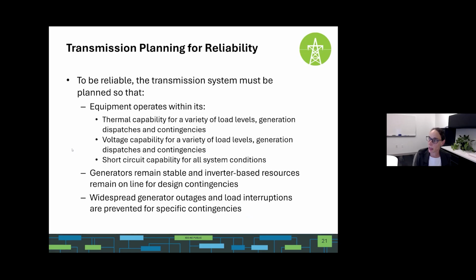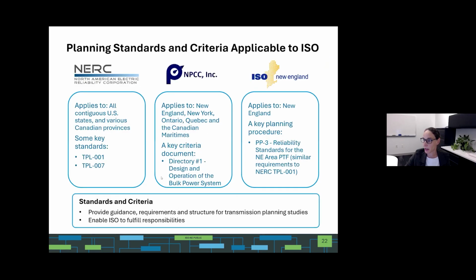To be reliable, the transmission system must ensure that all equipment operates within its limits: thermal capability, voltage capability, short circuit capability. We also want to make sure generators remain stable and inverter-based resources remain online for design contingencies. Brad's going to have more on those issues.